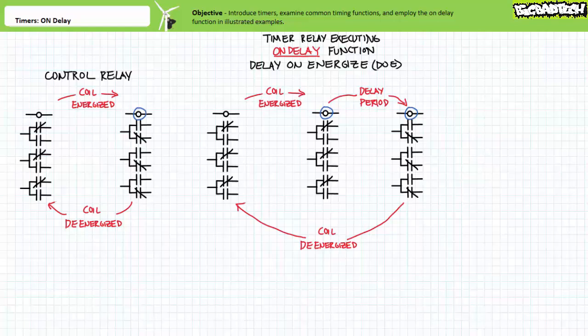The name really says it all. On-delay, or delay on-energize, means the contacts transition to their opposite states only after a period of delay of the coil being energized. Such a delayed transition could be used to stop or start another motor a measurable period after another motor is started, among numerous other applications, all serving to coordinate the sequential function of a complicated system.